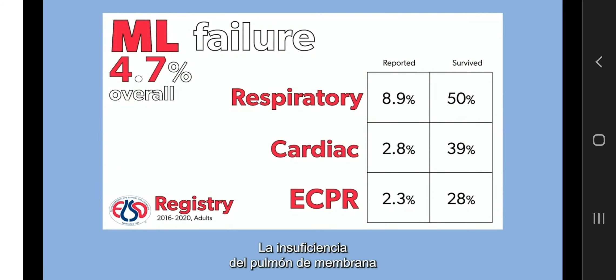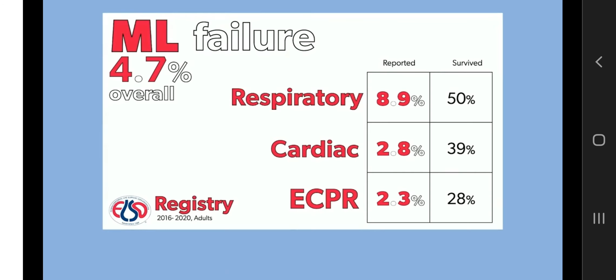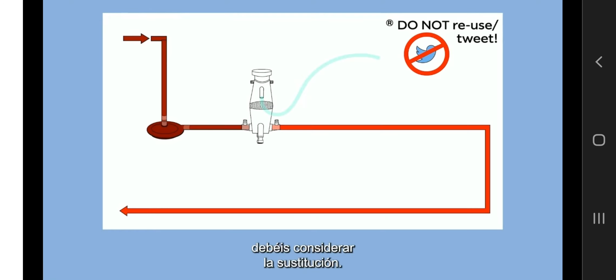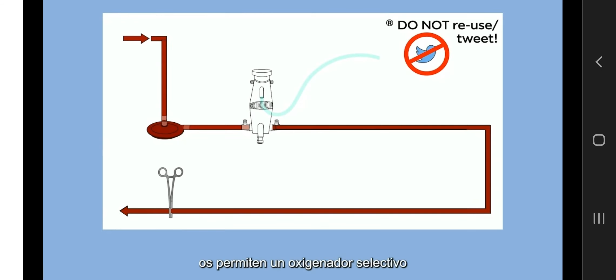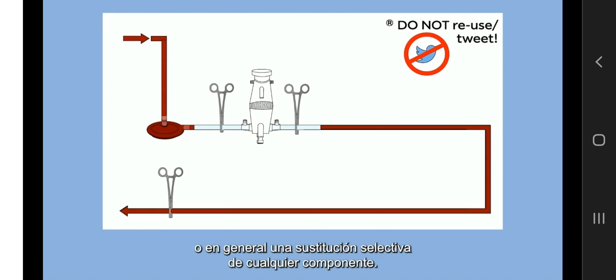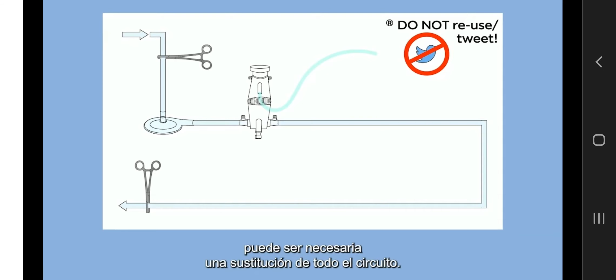This is the data from the ELSO registry. Membrane lung failure is one of the most common mechanical complications on ECMO, occurring frequently, particularly during respiratory support, probably due to the extended length of the runs and eventually due to lower blood flows. If your membrane lung is definitely failing, you need to consider replacement. Consider also that not all available systems allow a selective oxygenator replacement or, in general, a selective replacement of any component. So in some settings, a whole circuit replacement may be required.